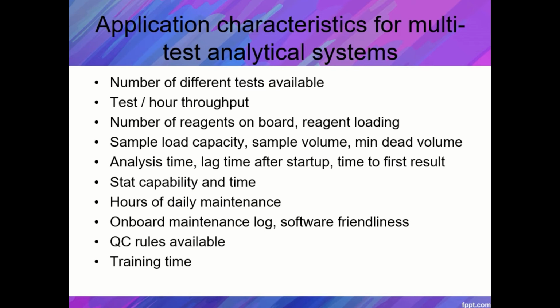So these are the application characteristics for multi-test analytical systems that need to be considered. Such as number of different tests available, test per hour throughput, number of reagents on board or reagent loading capacity, sample load capacity, sample volume and minimum dead volume, analysis time, lag time after startup, time to first result, stat capability and time, hours of daily maintenance, on-board maintenance log, and software friendliness.